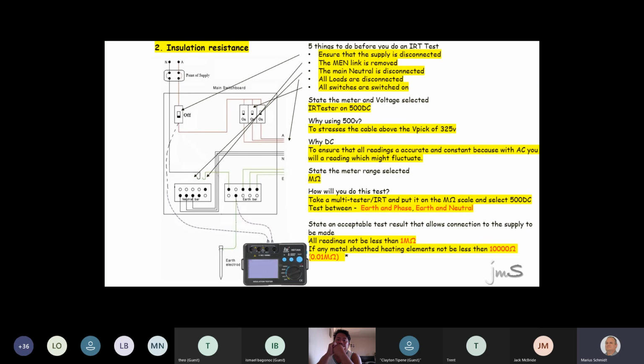Right. Now when you do a test, are you going to test between phase and neutral? Yes. No. Phase and neutral? No. What can happen if you test between phase and neutral? A, nothing, or B, damage equipment? Right. All your readings shall be greater than 1 megohm. Is that correct? Or, if you've got an element in, greater than 1 megohm or 10,000 ohms. Right, guys, please make note that 10,000 ohms is the same as 0.01 of a megohm.